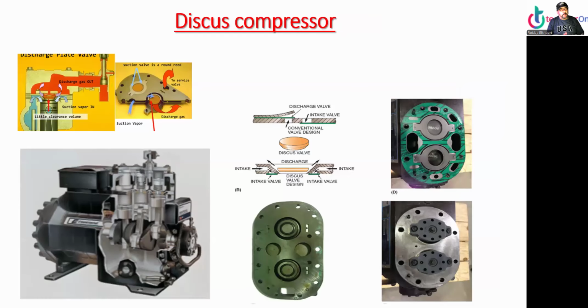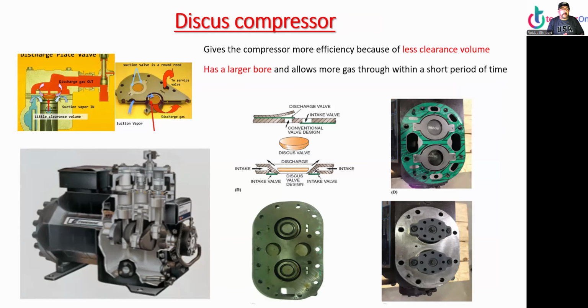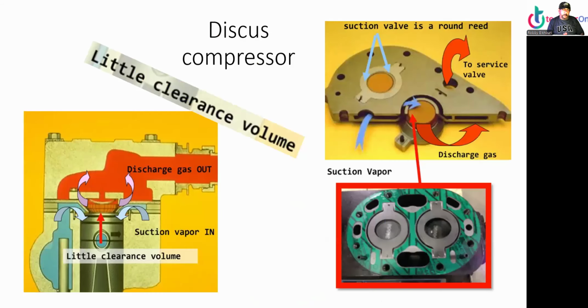All right, and speaking of discus compressors, there is a new style now. Discus compressors have a more efficient ratio because of less clearance volume. The clearance pocket has a larger bore to allow more gas through within the period. So that's a discus compressor.